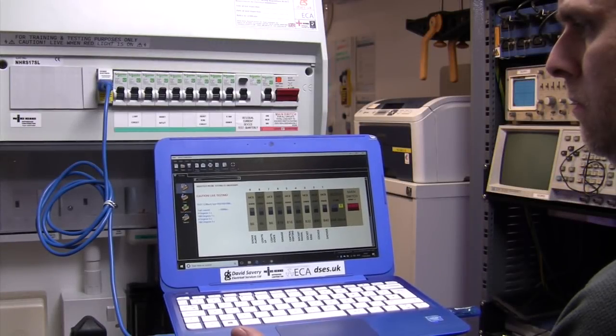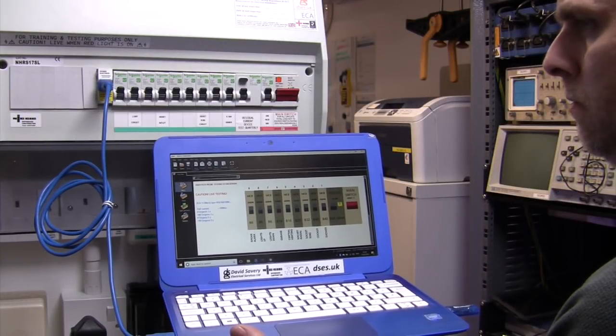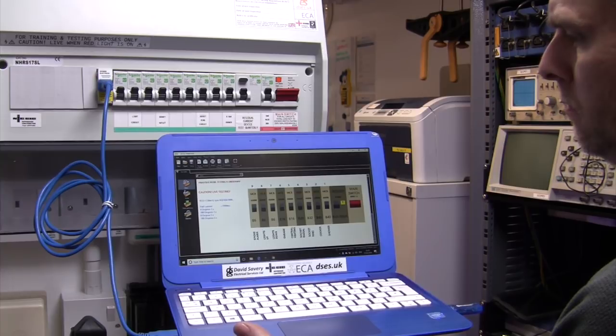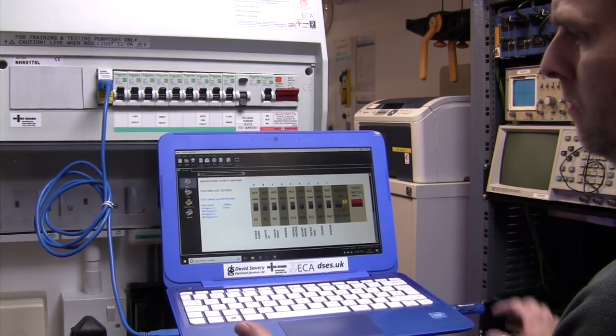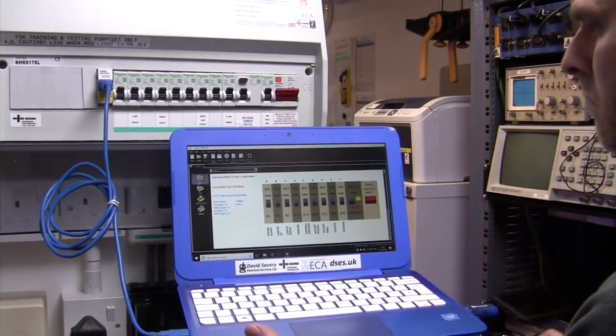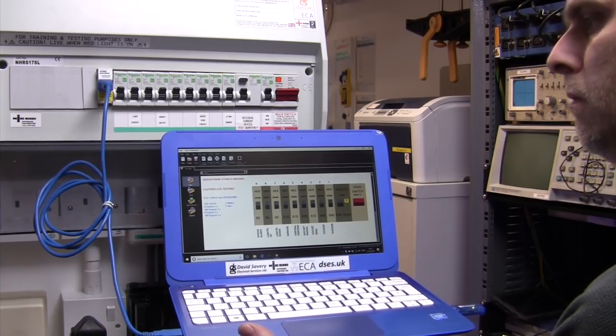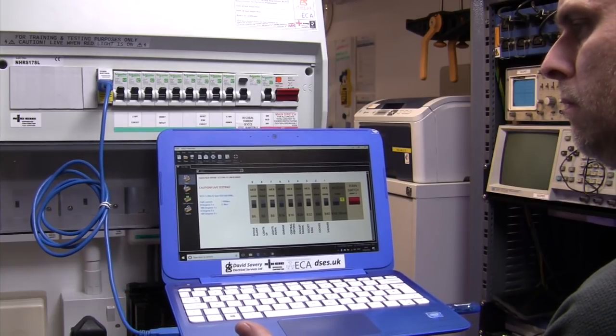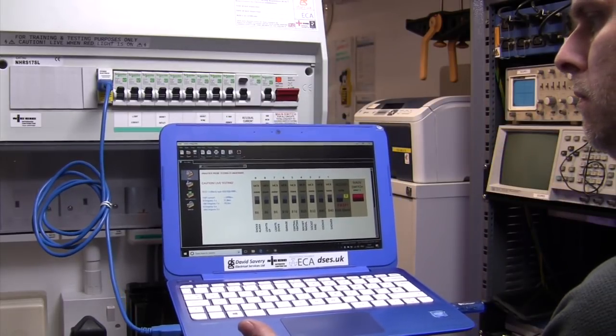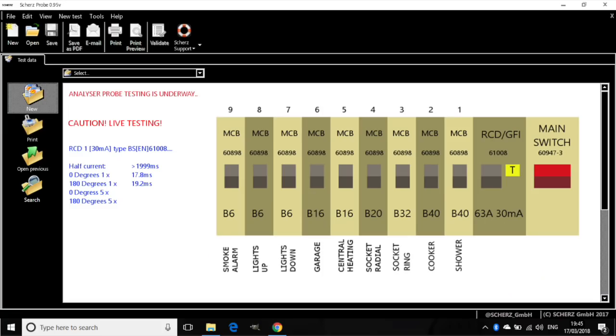Once the dead testing is complete, the consumer unit can be powered on with the device still installed in order for it to perform the RCD testing. The device will perform half times, 1 times and 5 times tests for 10 and 30 mA RCDs, and also supports 1 times testing of 100 mA RCDs, including time delayed variants. The manufacturer tells me that the market release version also supports ramp testing in the software, but the beta version I have here lacks this and I cannot demonstrate that functionality today.